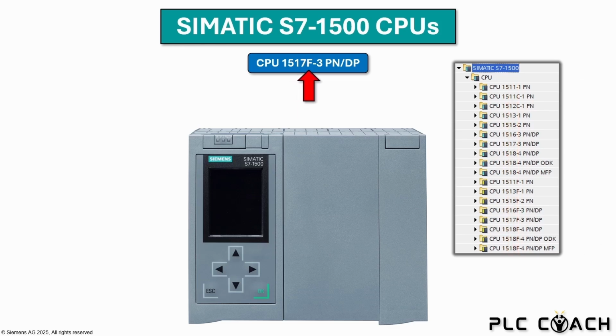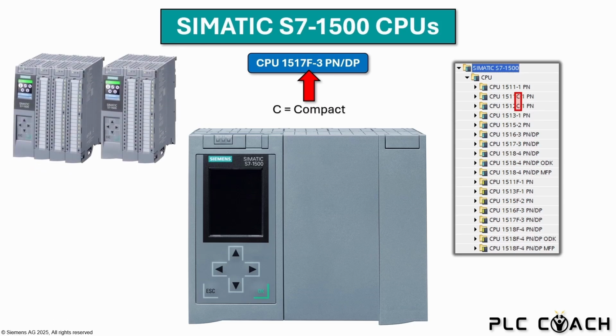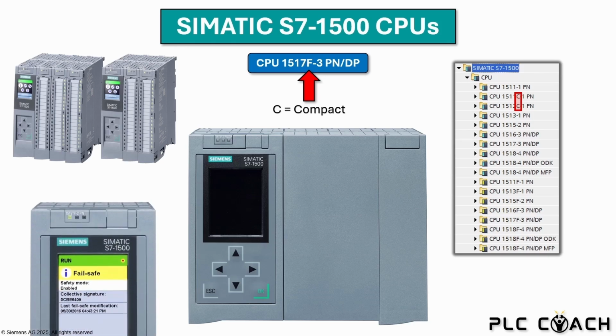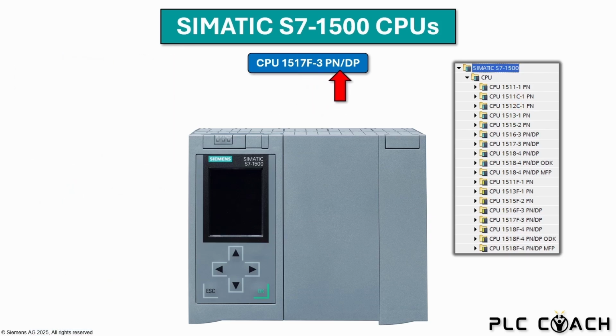The F in the name stands for failsafe. With a failsafe CPU, you can also implement safety functions like emergency stop. If you find a C in the name of your controller, it means it's a compact PLC. These already have pre-installed input and output modules. If you find a T in the name of your controller, it means it's a technology CPU. A T CPU is designed to handle advanced technological tasks in addition to standard functions. For example, advanced motion control. The remaining numbers and letters provide information about the available interfaces of the CPU.